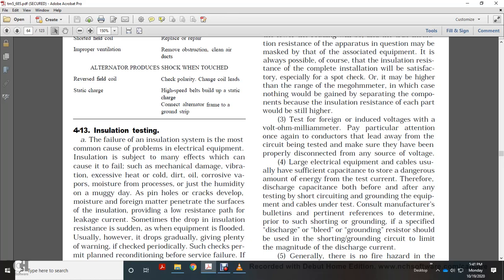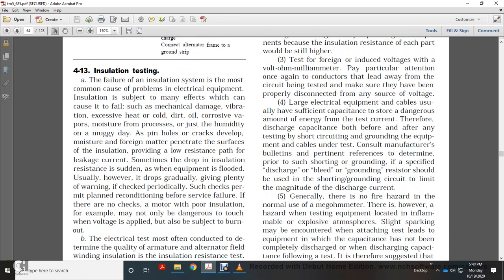Test for an induced voltage with a volt-ohm-milliammeter, paying particular attention to the conductor leads away from the circuit being tested, to make sure they have been properly disconnected from any sort of voltage. For large electrical equipment, cable usually has sufficient capacity to store a dangerous amount of energy from the testing.